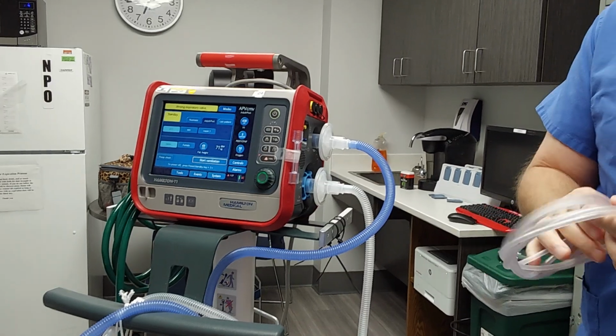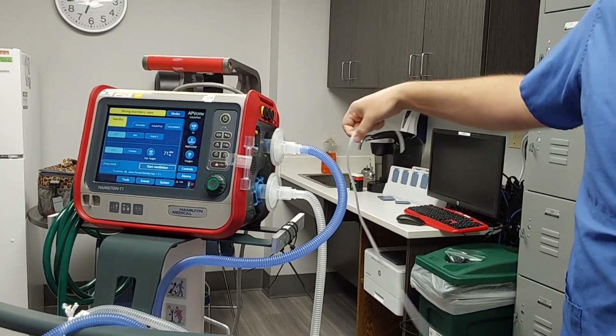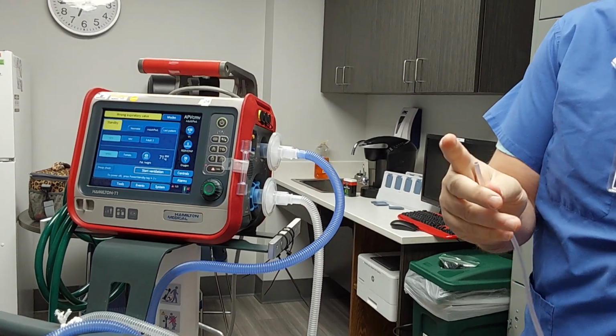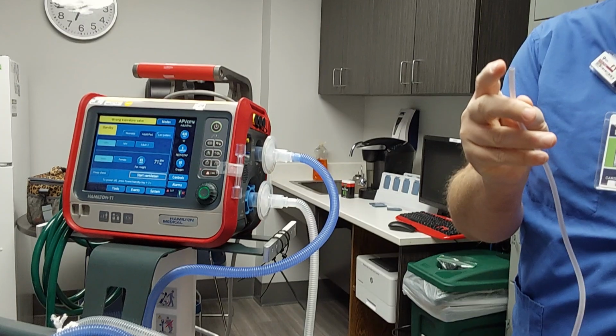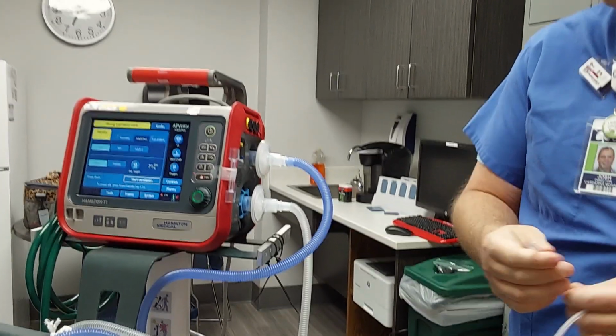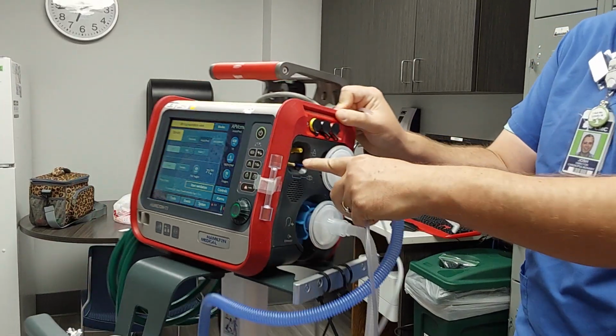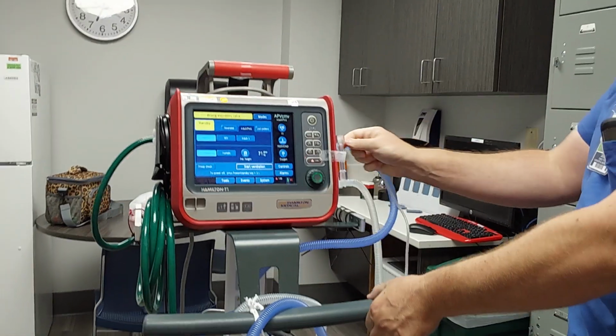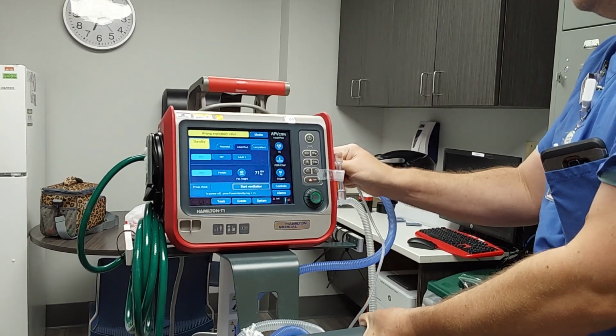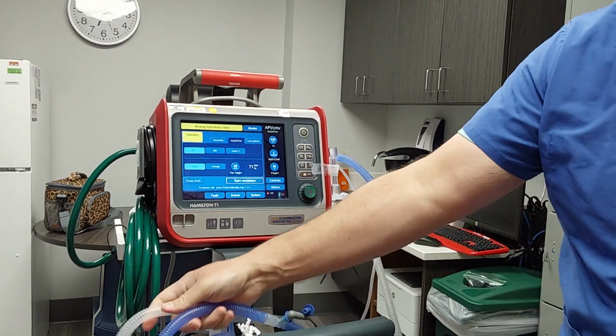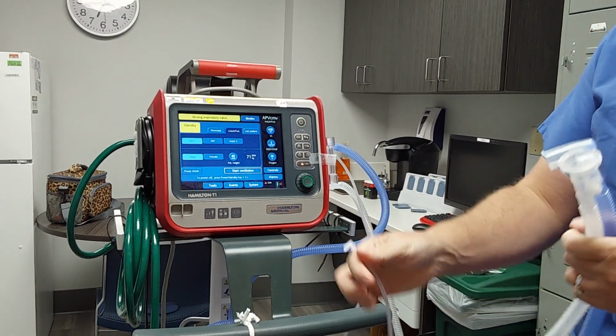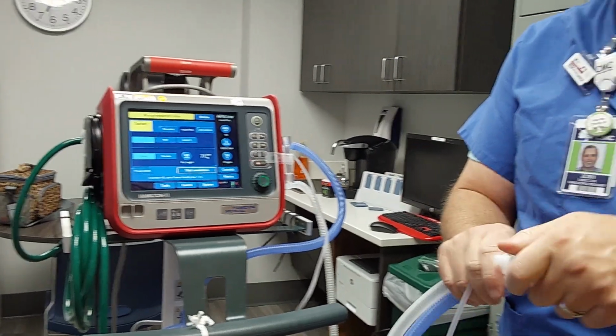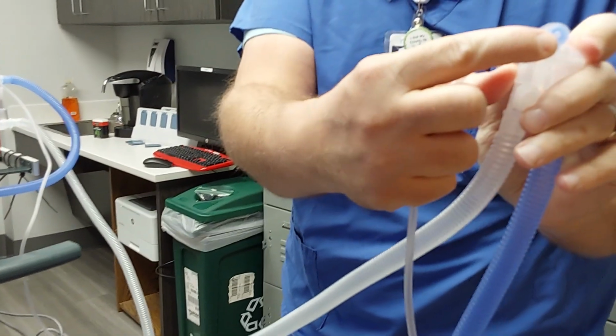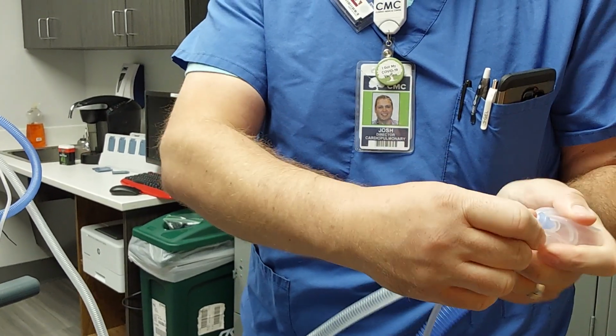So to do CPAP, you need a pressure line. This pressure line comes in your circuit. There's a larger end on it when you pull it out of the circuit bag, and you just cut that off. That's going to go on your blue stem. This is a pressure line, again, just to monitor pressure. So it does disable some of your alarm functions in non-invasive. The end of your pressure line, there's a little hole right here. Just push that in, make sure it goes in really good.